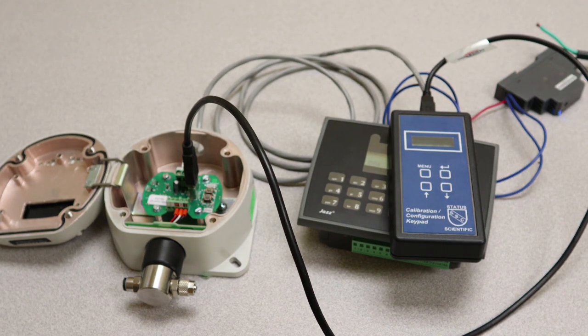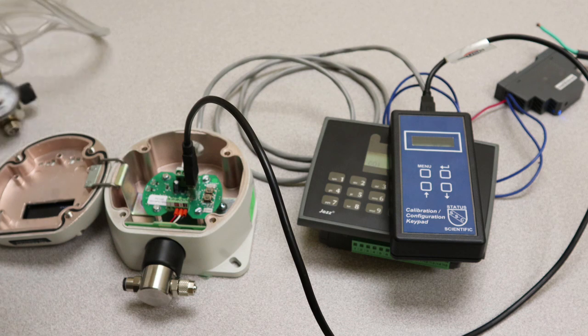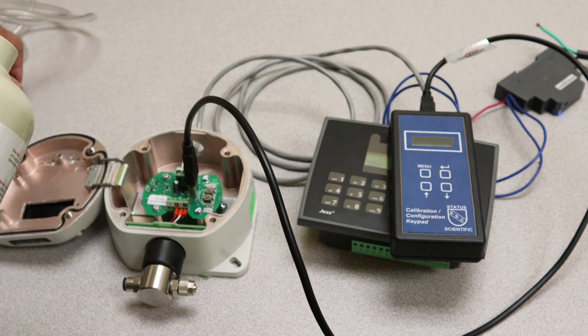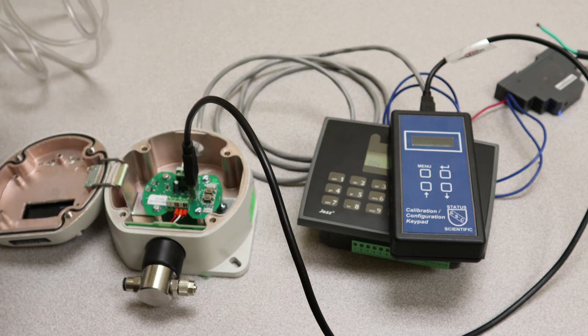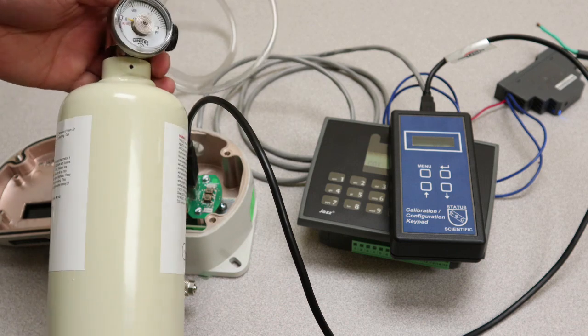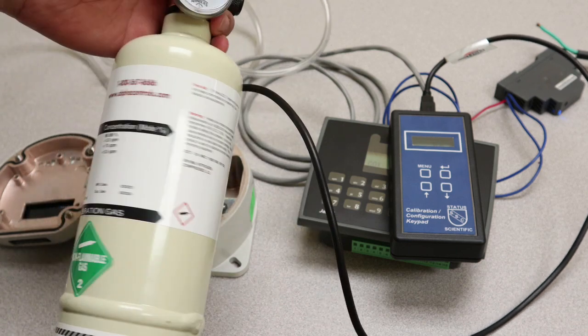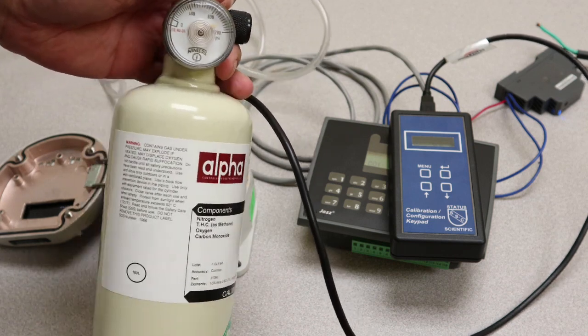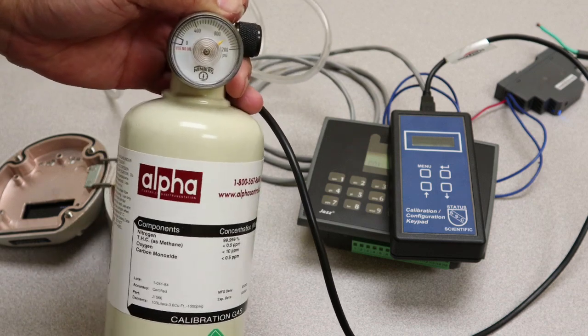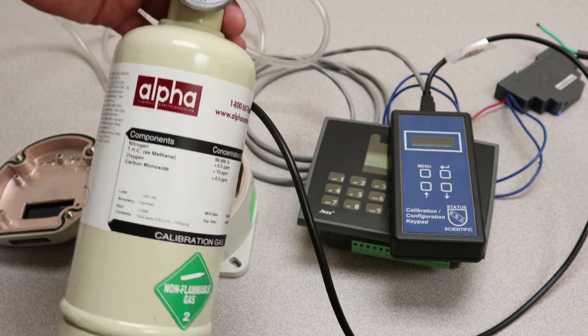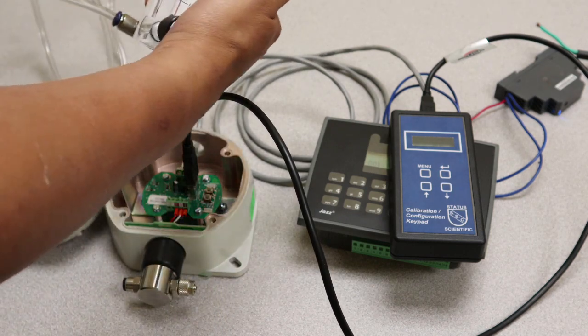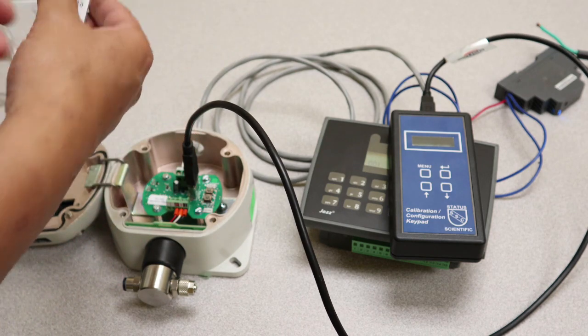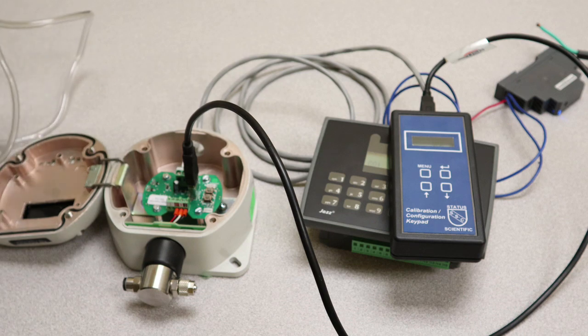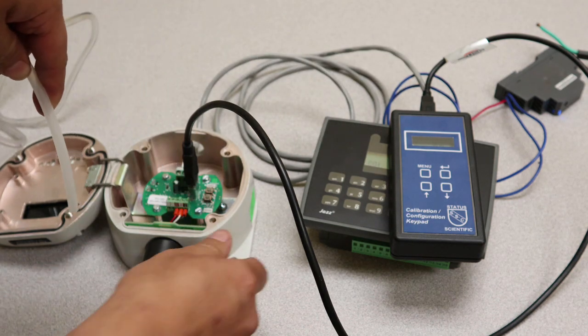So first we're going to take the nitrogen, and we're going to connect the nitrogen to the regulator, making sure the regulator is off. And we're going to plug this in. And as you can see, the gauge came alive, meaning that I do have gas in my bottle. The gas is then being fed to a flow meter, which is then we're going to have a tube that you can connect to the right side of the gas connection.